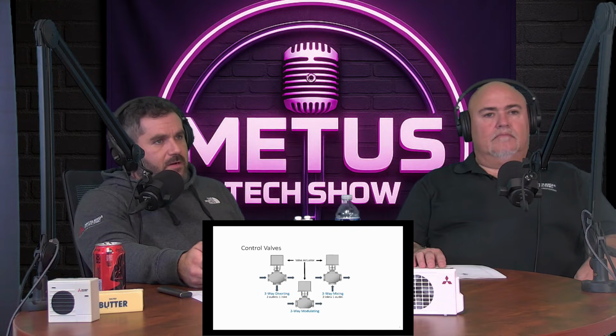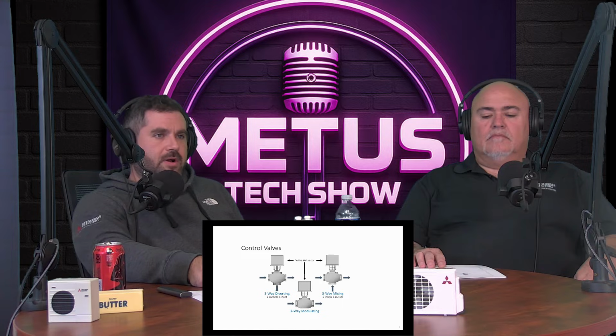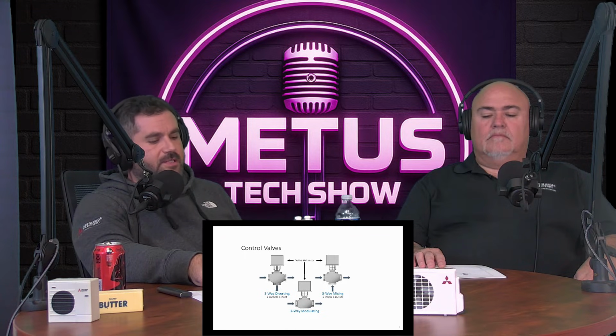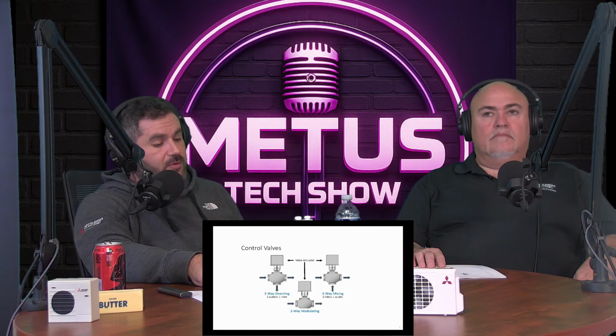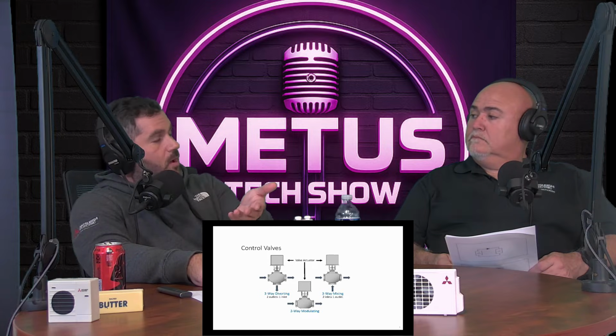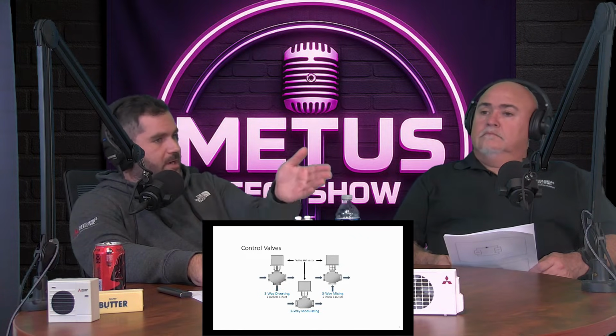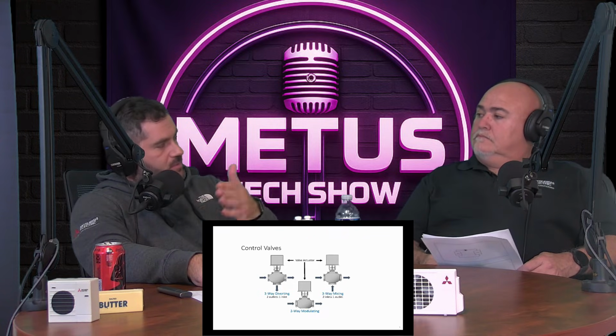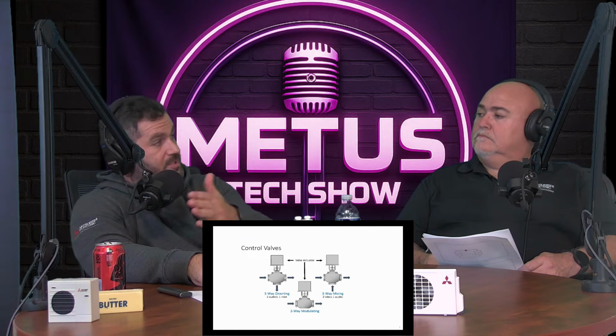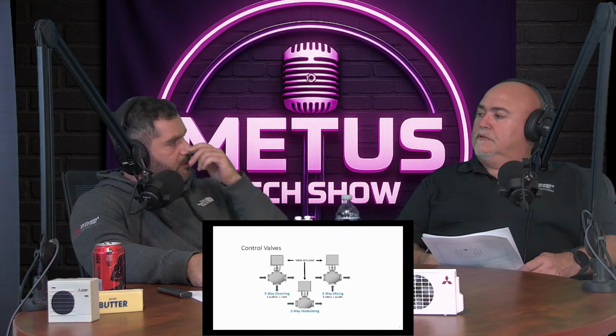Yeah. So, in addition to expansion tanks, we've got our basics as far as feeding the system, making sure we maintain proper pressure. But how do we actually control the water as it flows through the system? There are different control valves, and the basics are just a three-way diverting valve, where you have a single inlet, and depending on the position of that valve, it gives you two separate outlets. So let's say you have a system where, when it is not energized, you want it to flow in the direction of a water heater, but when it becomes energized, you want it to flow in the direction of a heat source. Right. So that two-position valve is not so much open-close, it's more open to one route, open to another route. So that would be a diverting valve.